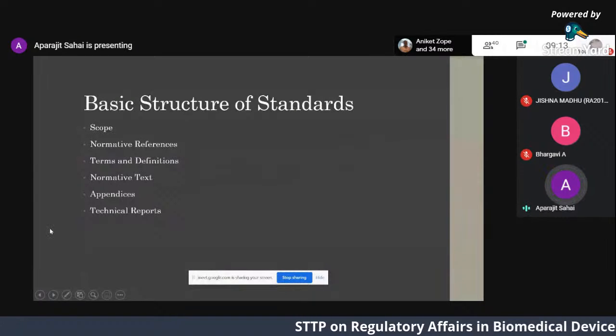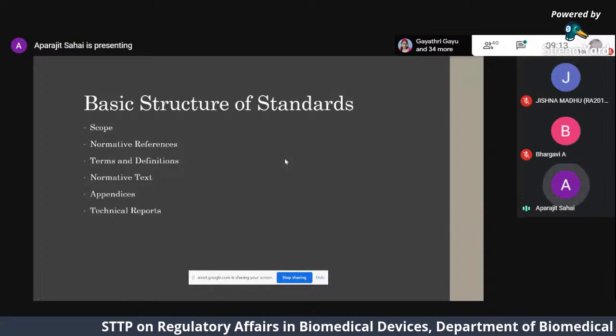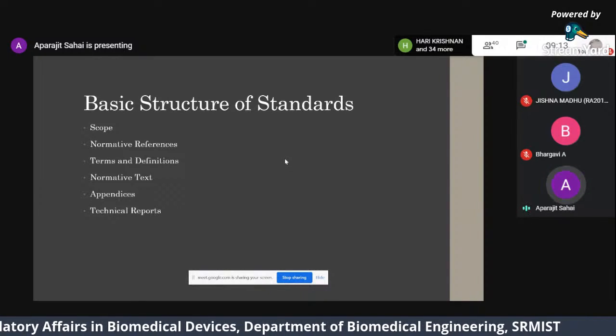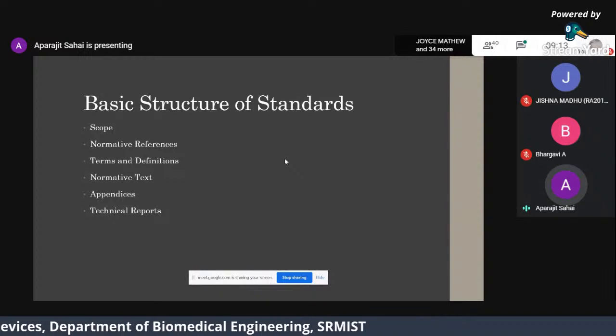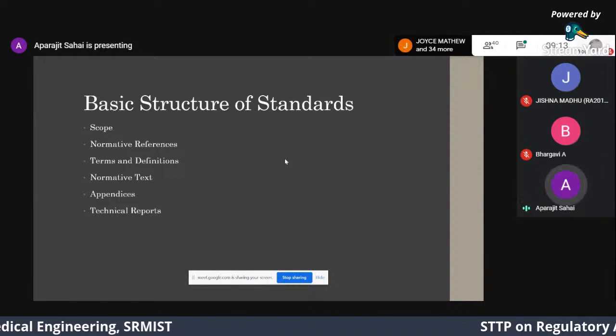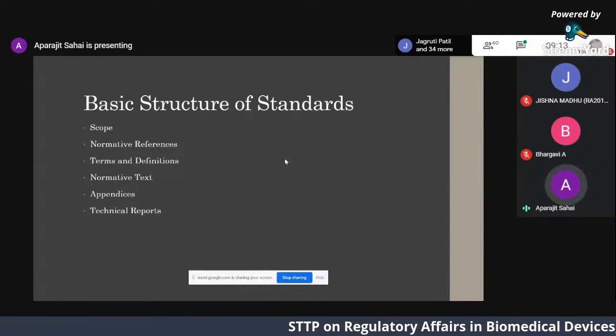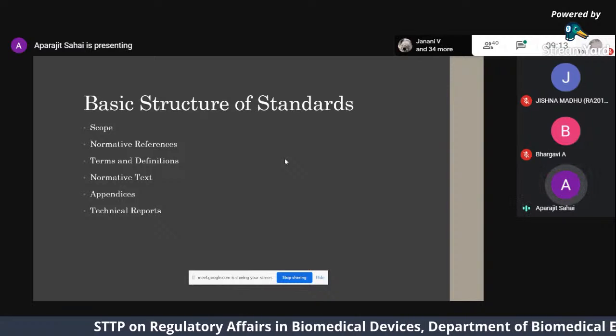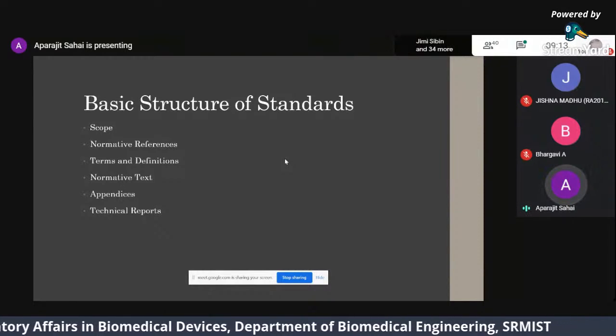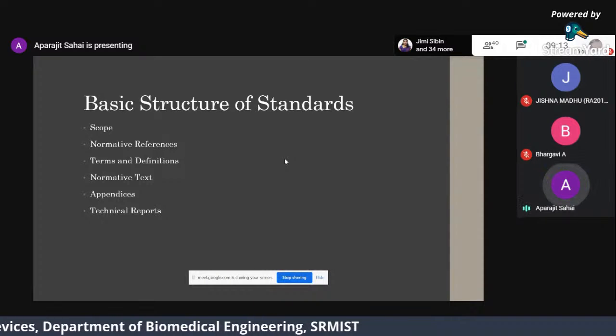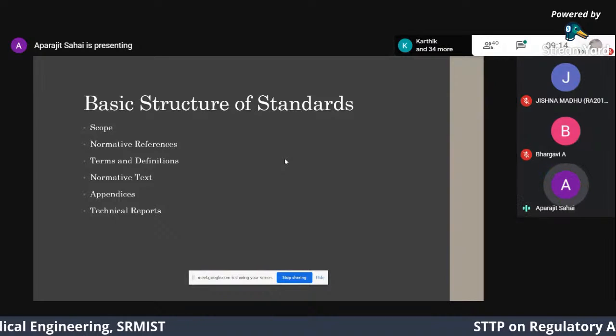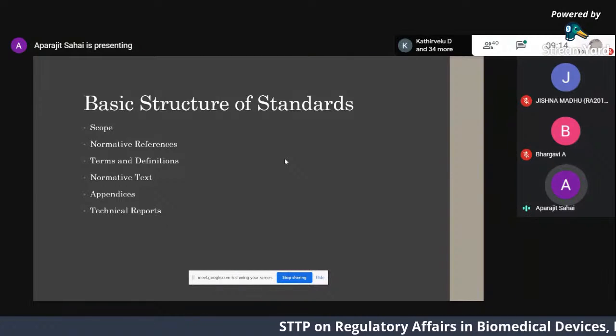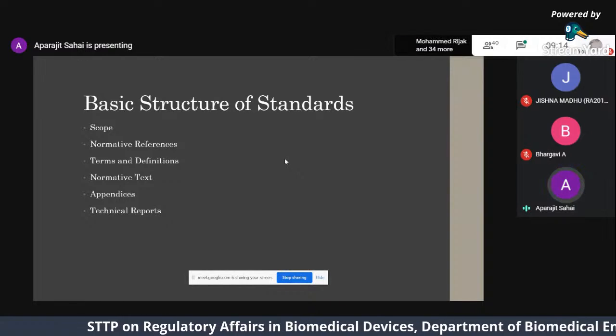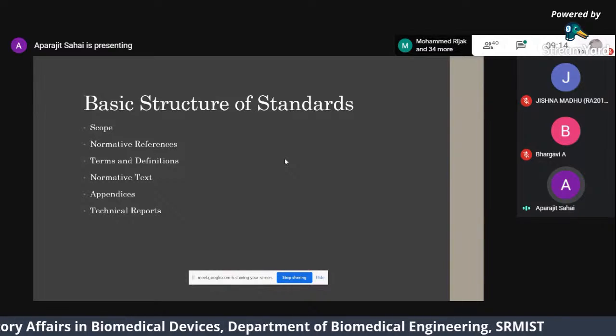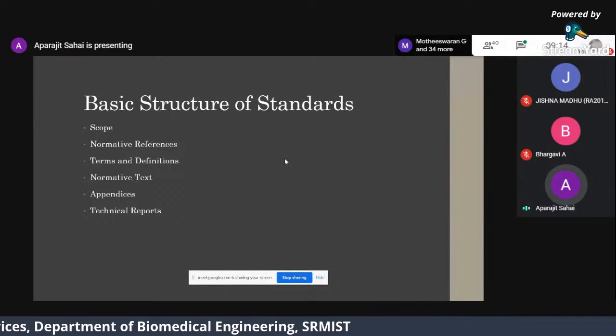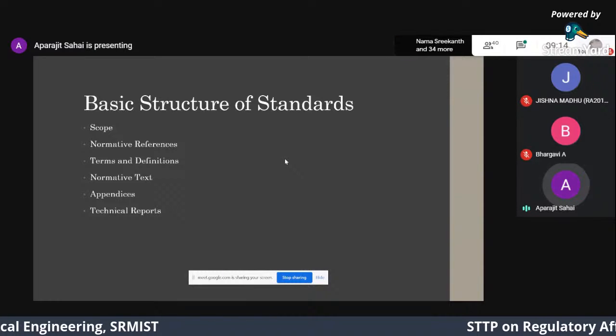And then there are technical reports. For example, ISO 14971, which is the risk management standard, has a technical report that goes with it, which is 24971. In addition to the annexes, the technical report explains how the standard can be applied and how you can comply with it. There are technical reports not just for 14971, there are technical reports for 60601-1, if I'm correct, and also for 13485. These technical reports explain to you how you can apply the standard. They don't really lay out the requirements. The requirements are in the actual IEC ISO standards, not in the technical reports. But the technical reports that go with specific standards explain how to apply those standards. So that's about it for the basic structure.